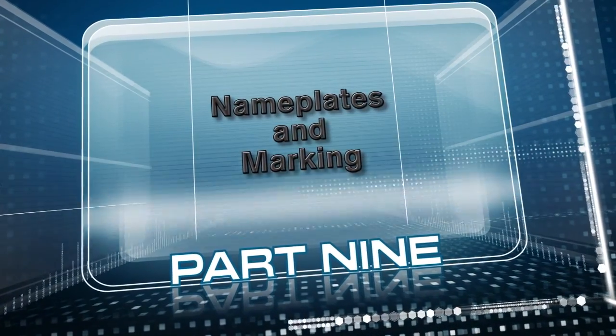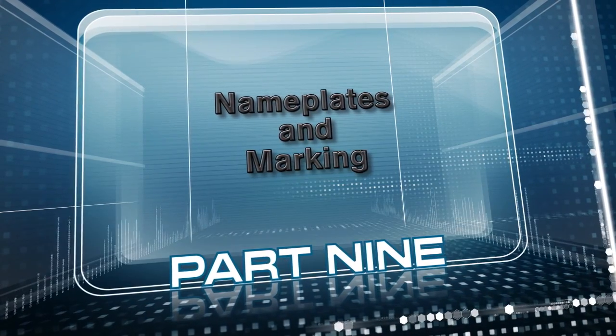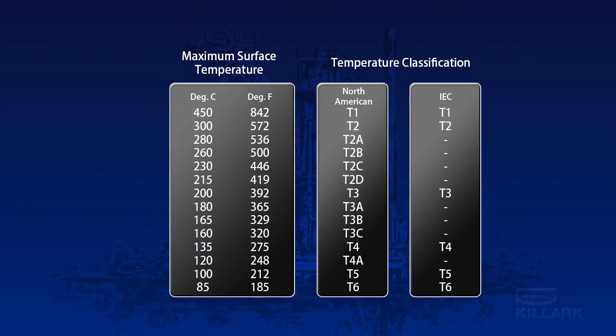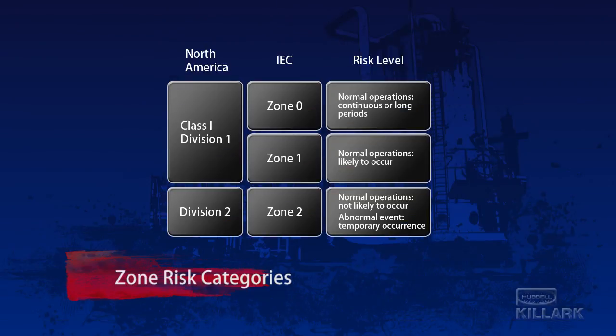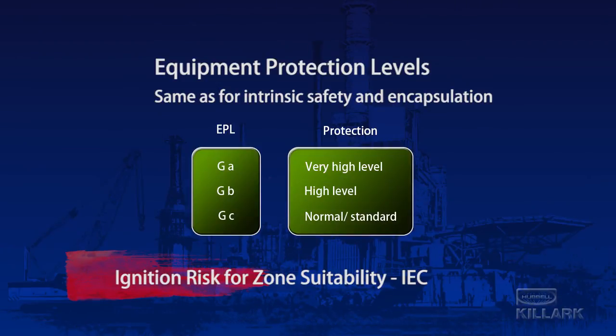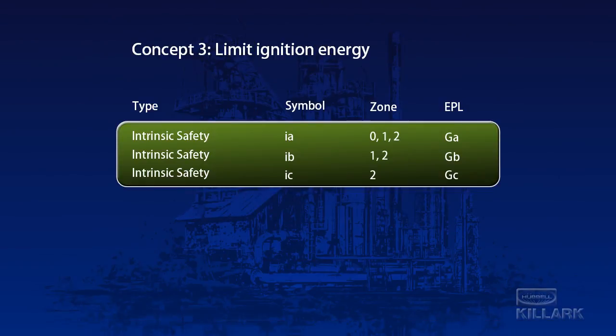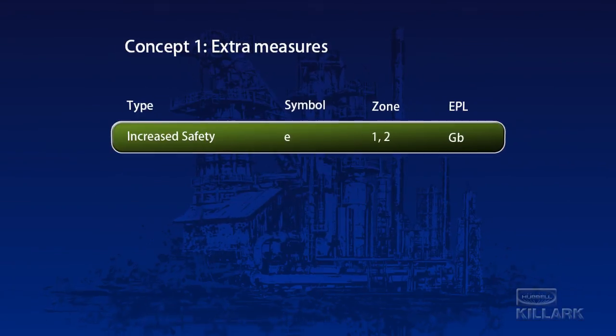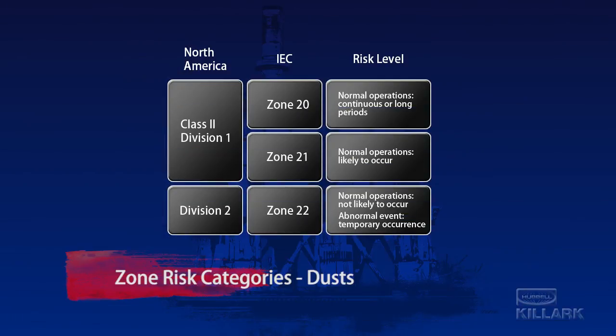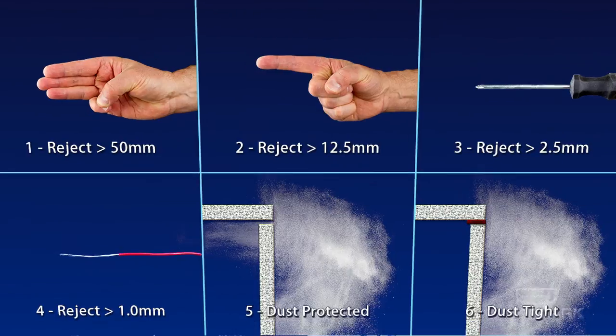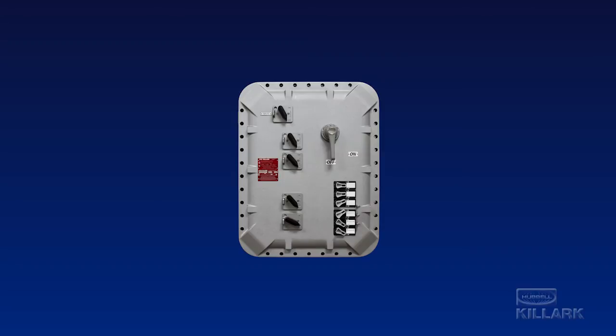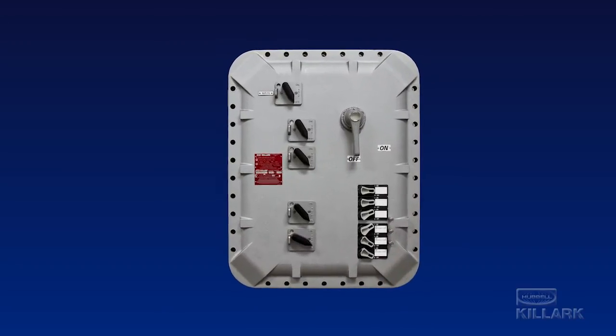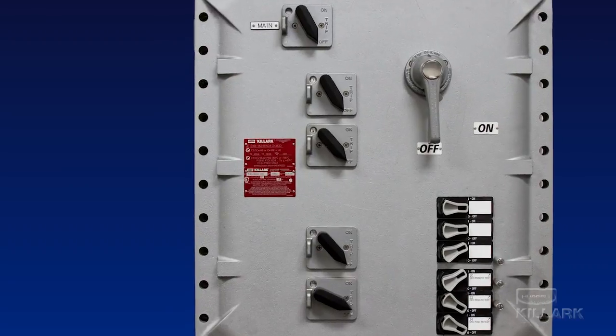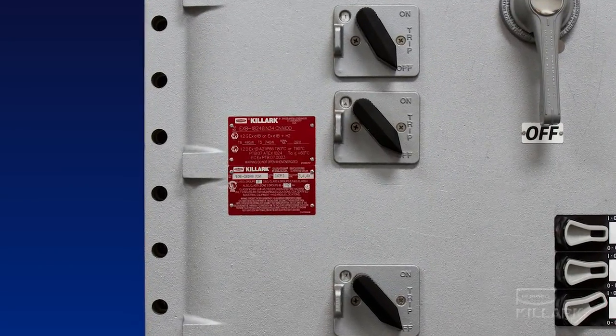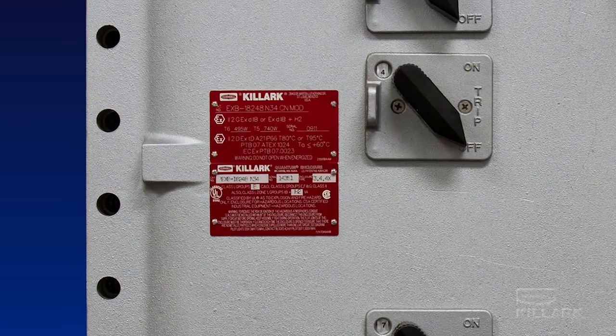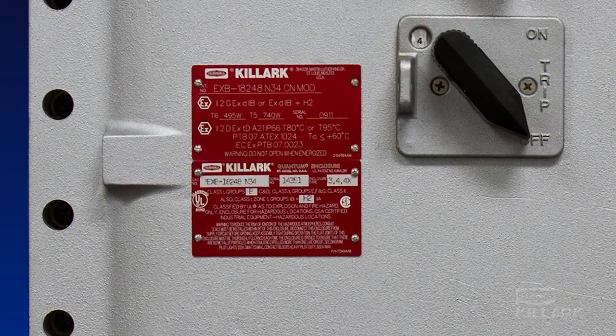Part 9. Nameplates and Marking. Without doubt, quite a range of information is required in order to properly select and specify the protection methods, types of equipment, and precise products to be used in a location that has been classified as hazardous. Certificates and other documentation are absolutely important, but that information must also be easily available directly on the equipment for installation personnel, inspectors, maintenance crews, and field safety engineers.